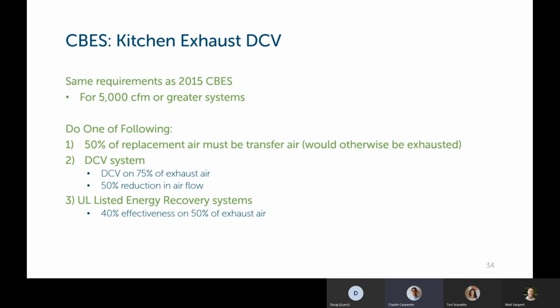One of the more common strategies is number 2 here, which is a demand control ventilation system, where the hood can modulate its speed based on the temperature of the exhaust air going through it. So you would need to have this demand control ventilation controlling 75% of the exhaust air in your kitchen. You add up all the exhaust rates of all the kitchen hoods together, and the system must be able to reduce the flow down to 50% or lower.